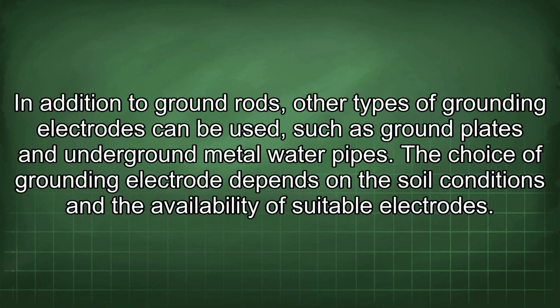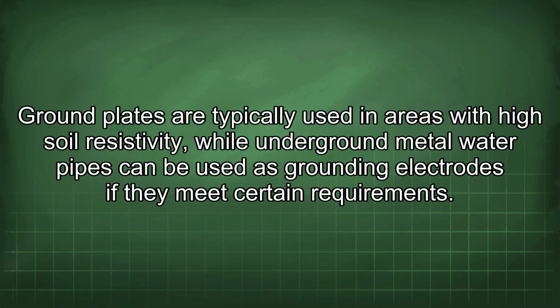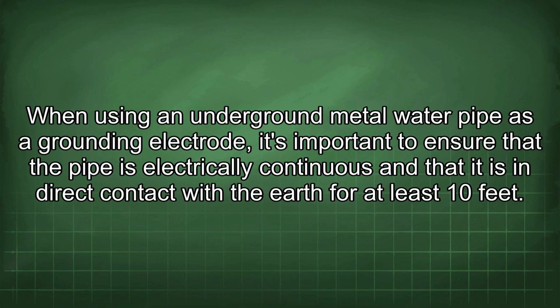It's crucial to find a solution that meets the power company's requirements while also ensuring compliance with the NEC and prioritizing safety. In addition to ground rods, other types of grounding electrodes can be used, such as ground plates and underground metal water pipes. The choice of grounding electrode depends on the soil conditions and the availability of suitable electrodes. Ground plates are typically used in areas with high soil resistivity, while underground metal water pipes can be used as grounding electrodes if they meet certain requirements. When using an underground metal water pipe as a grounding electrode, it's important to ensure that the pipe is electrically continuous and that it is in direct contact with the earth for at least 10 feet.